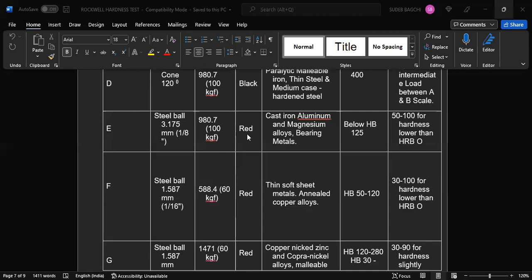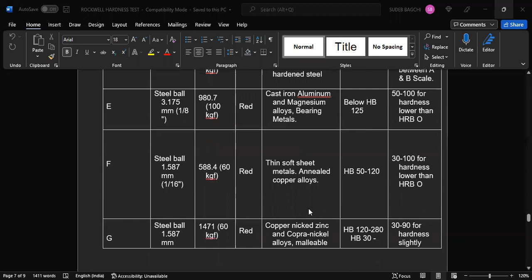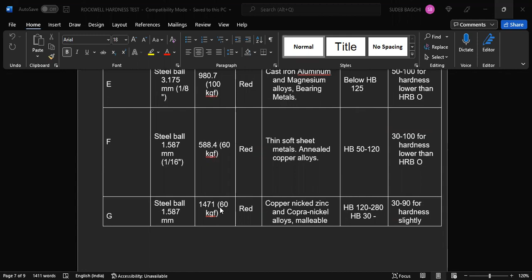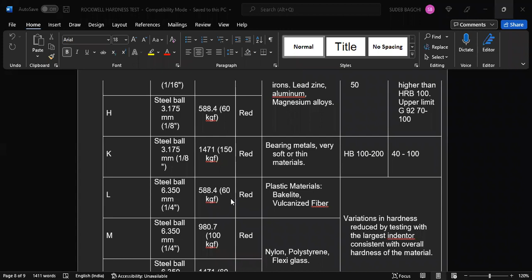Similarly, for cast iron and aluminum, we use comparatively larger steel balls of 3.175 mm and 100 kg load, on the red scale. A steel ball of 1.587 mm is used for thin soft metals, aluminum and copper alloys, with 60 kg load on the red scale, for copper, zinc and nickel alloys, malleable alloys. So there are many other applications of different types of indenters and charts as well as loads, which you can select as per your requirement.